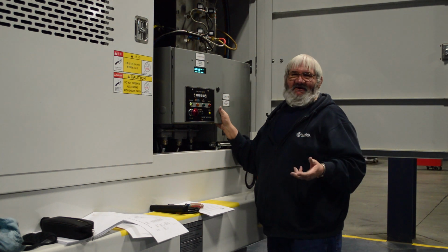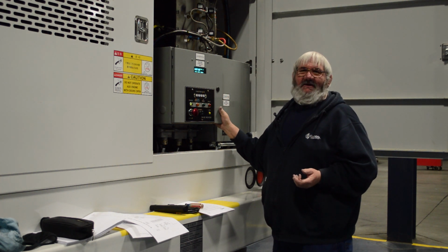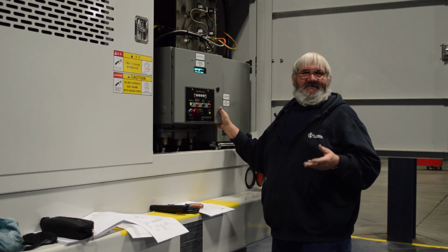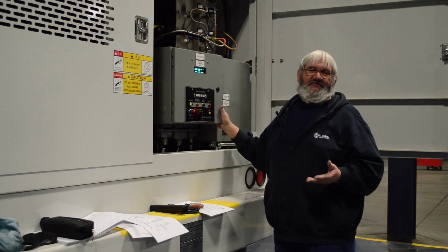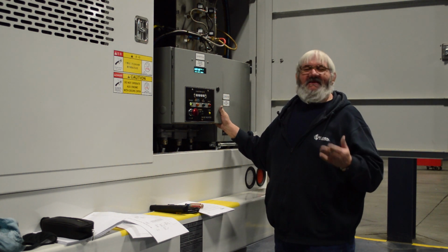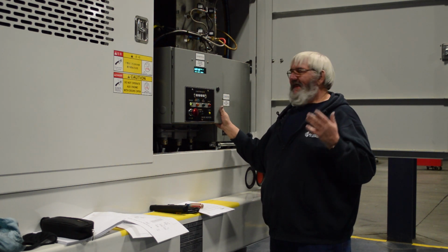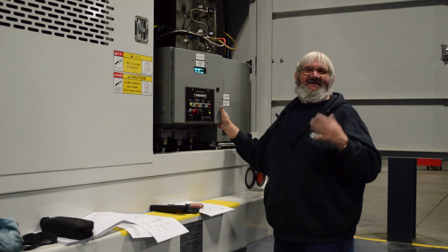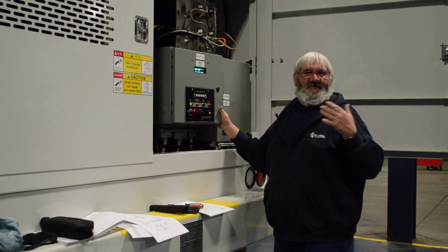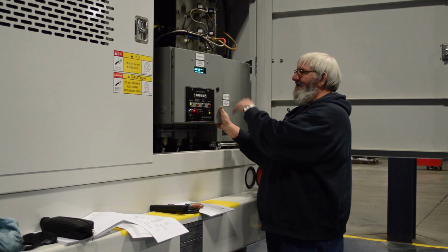Now, typically what I see on the fuel side is this particular test is a static test. Several times the fuel pump and fuel system can maintain a static fuel pressure test. If your system checks out okay in a static test, the next thing that you want to do is do an actual heater run or heater burn. What happens in a heater burn, this is actually a flow test. Several times the fuel pump can do a static test, but it fails a flow test.